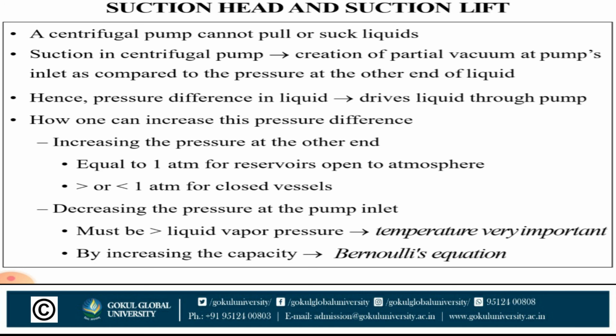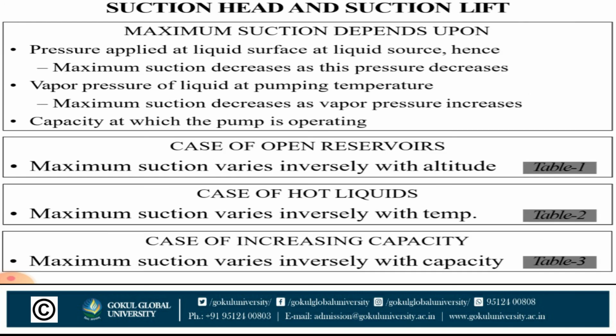When the capacity increases, see the Bernoulli equation. Maximum suction head depends upon the pressure applied at the liquid surface at the liquid source, so maximum suction decreases as this pressure decreases. It also depends on the vapor pressure of the liquid and pumping temperature: maximum suction decreases as vapor pressure increases. And on the capacity at which the pump is operating. In the case of an open reservoir, maximum suction varies inversely with altitude. In the case of hot liquid, maximum suction varies inversely with temperature. In the case of increased capacity, maximum suction varies inversely with capacity.